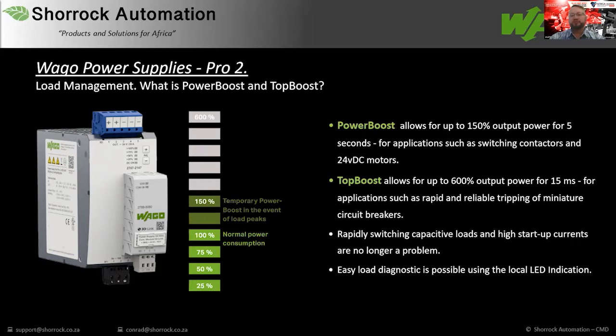Easy load diagnostics is possible via the local LED indication. And I'd like to highlight that we've used this before and it really works well. When we get to a customer and he's got a problem in his power supply, you'll see on the front of this power supply there, we have a signal that says DC OK, greater than 25%, greater than 50%, greater than 75%, and greater than 100%. This is an indication of your actual load that the power supply is currently running at. We often buy a 20 amp power supply or a 10 amp power supply, not realizing that it's running at 90% of the load or 100% of the load, or more often it actually happens that it's running a bit over.